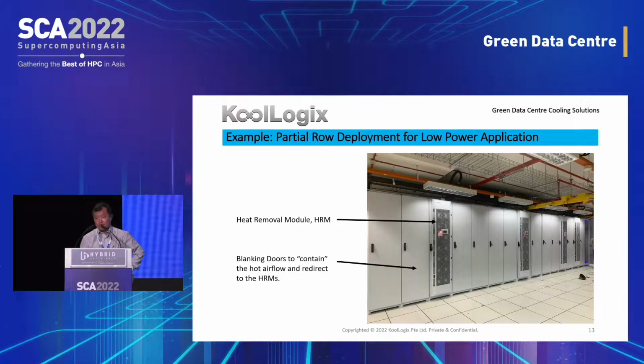This provides a lot of configuration flexibility and cost-saving opportunities. This is a picture of our latest implementation, where each rack power dissipation was about 5 to 7 kilowatts, but it's not air-cooled anymore—they used HRMs. Only 4 HRMs are shown here, utilized to cool more than 12, maybe 14 racks. The total power in this picture is designed to match the 20 kilowatt HRMs.